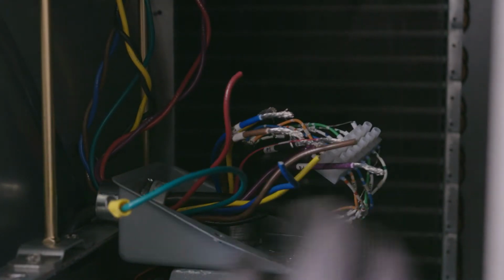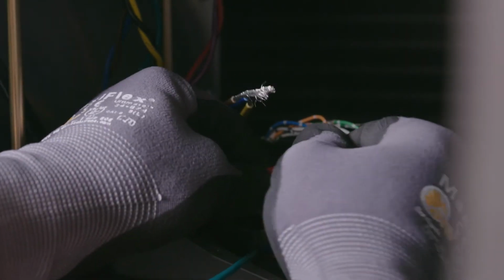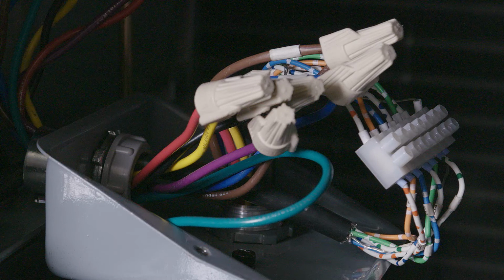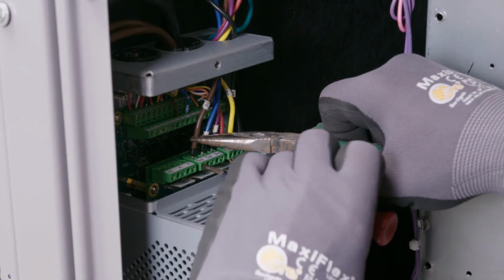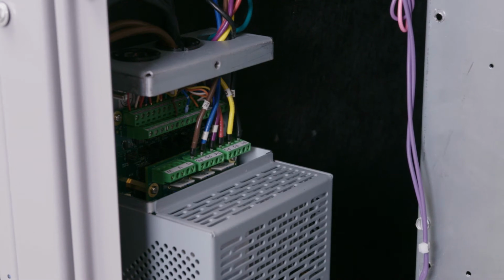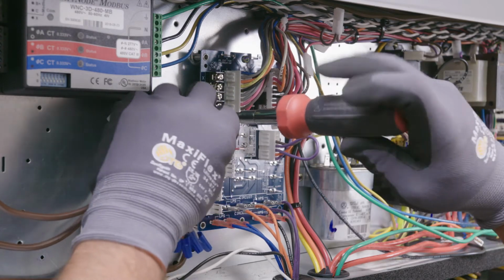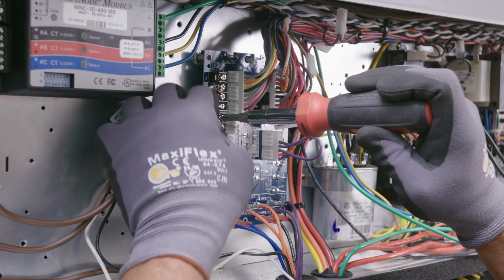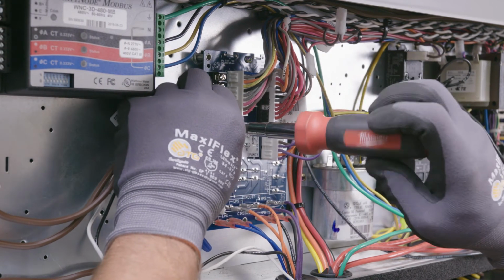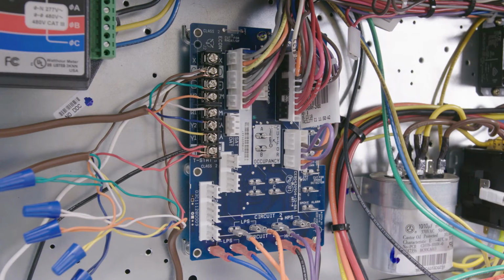Next, connect the motor power cable from the motor controller to the smart motor at the motor junction box. The motor power cable is labeled P1 through P6 and includes the grounding wire. Again, refer to the wiring schematic as needed. Complete this step by making sure that all the grounds are connected securely on both the smart motor and the motor controller. Follow these steps if the motor controller will be used to control the RTU. First, disconnect the wiring from the thermostat and connect it to the motor controller per the wiring schematic. Next, connect the RTU wiring from the motor controller to the RTU thermostat input terminals or wires.